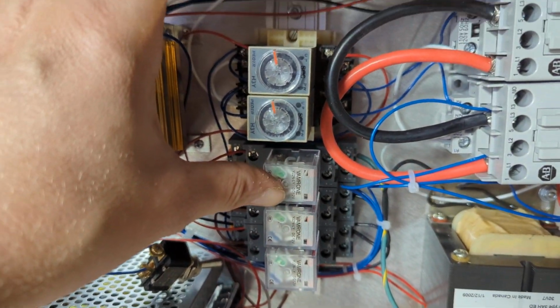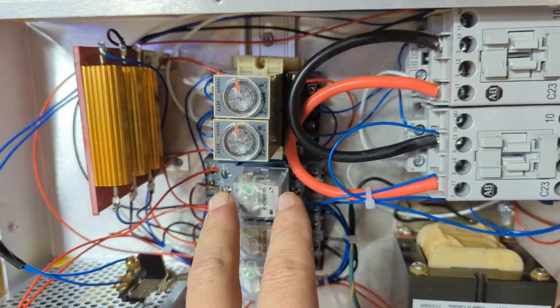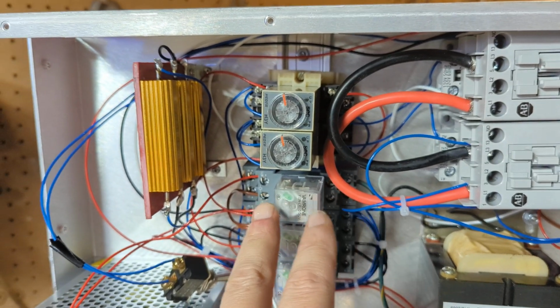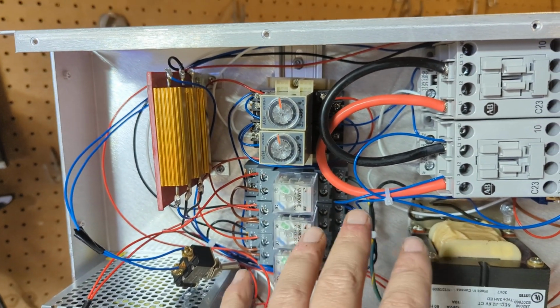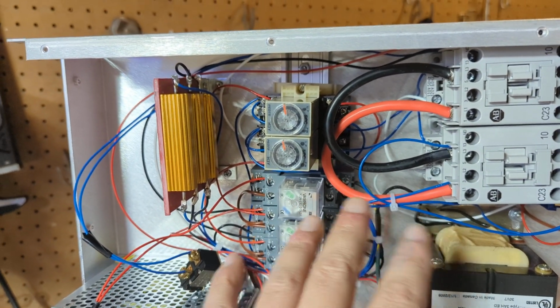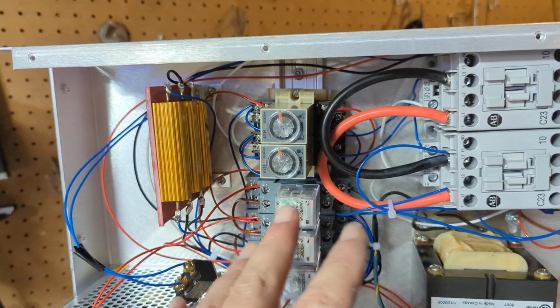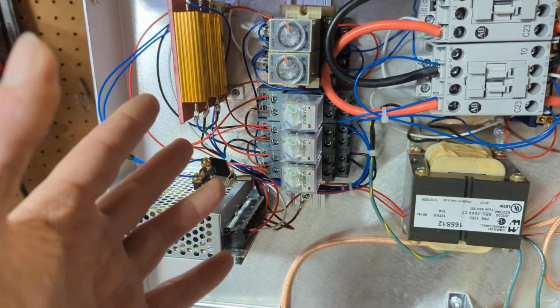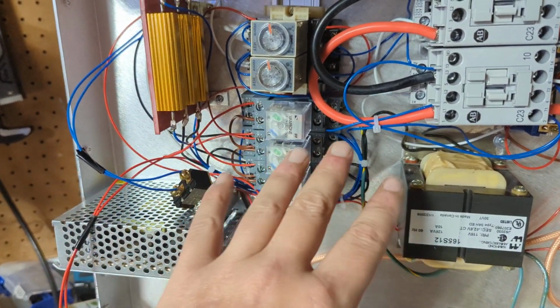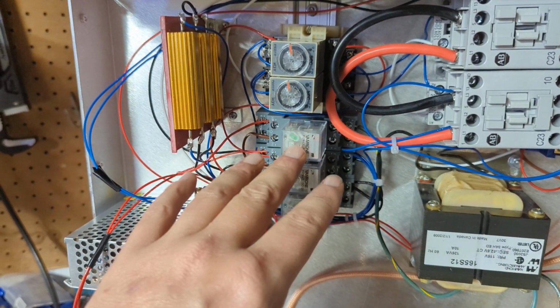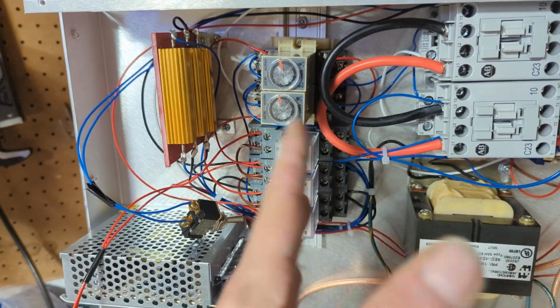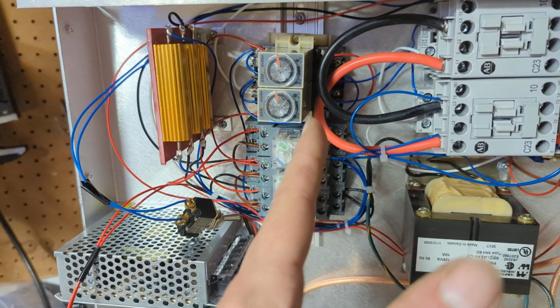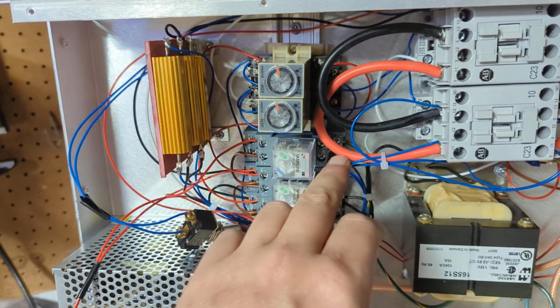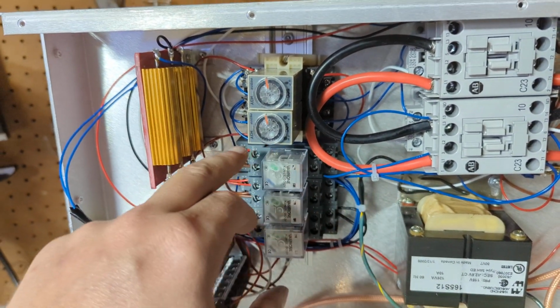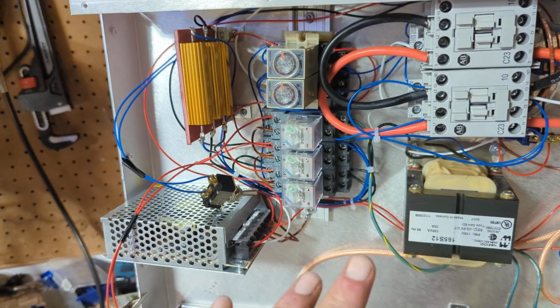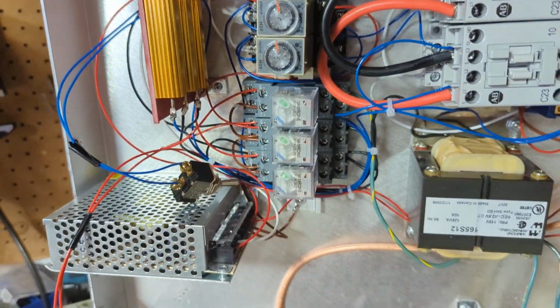So all this relay does is bypass the 20K 100-watt resistor. The tube should never ever be disconnected from B negative. Otherwise the tube goes floating, out of control. You don't want to have that. So the tube always, even at the time the relay clicks over, the tube should never be out of control. The tube should always be connected physically to B negative, whether it's through a resistor or through a relay.